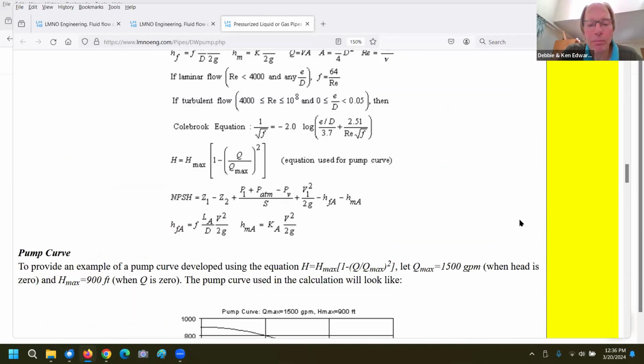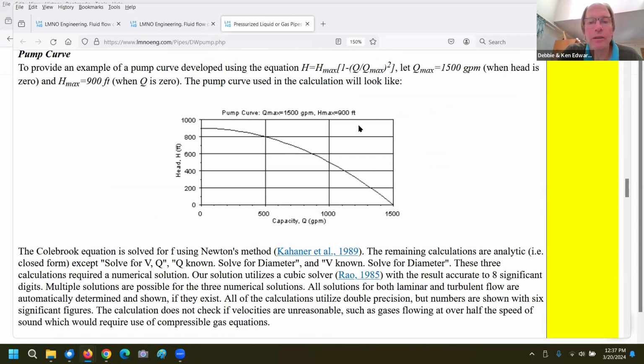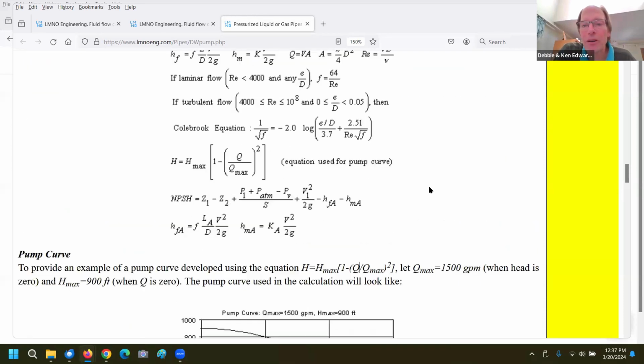And so we simulate pump curves just with a simple equation like this. Now, if you go to a pump curve supplier or manufacturer, they're going to give you a curve, and it's not going to quite look like this. This is just a second order approximation of a generic pump curve. But you can put into our program the max point for the head and the max point for the flow, and our program will fit a nice parabolic curve through those points.